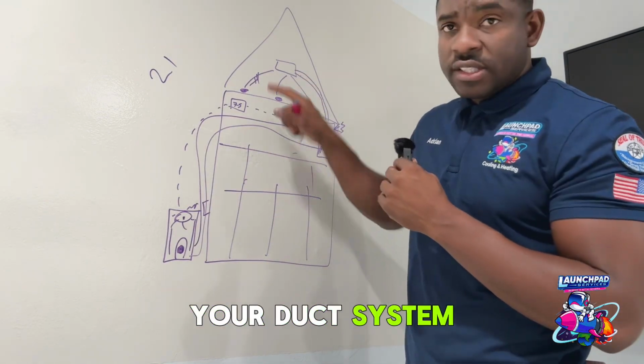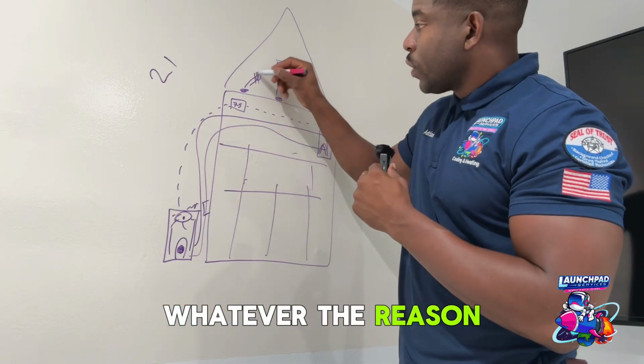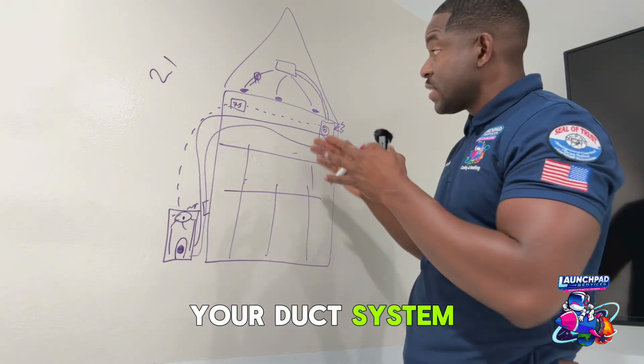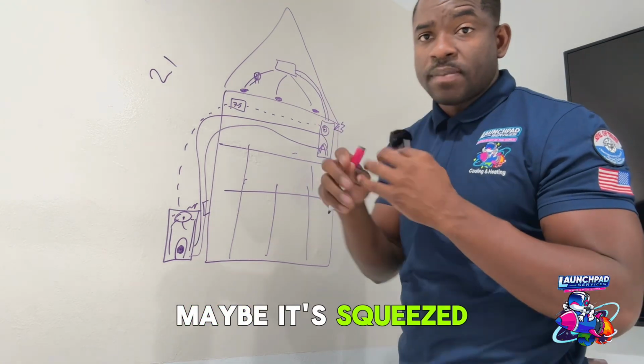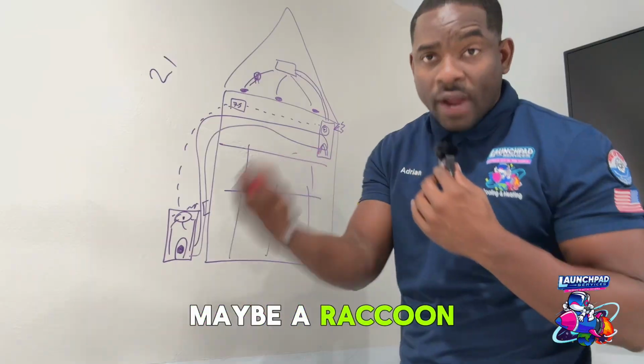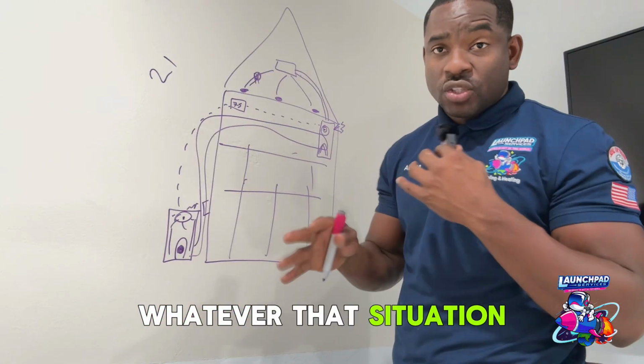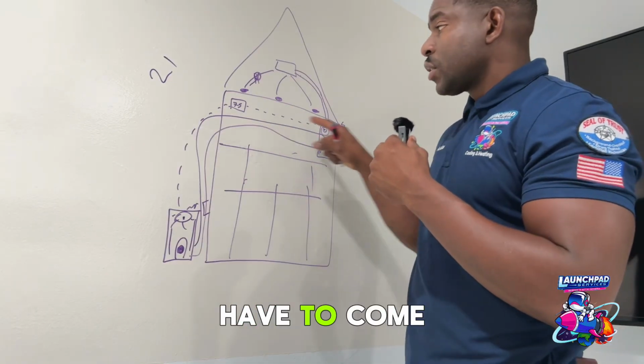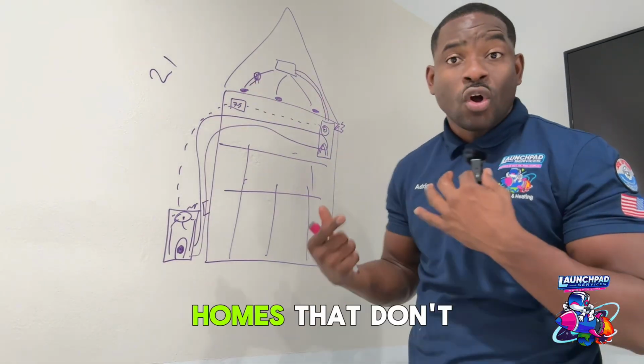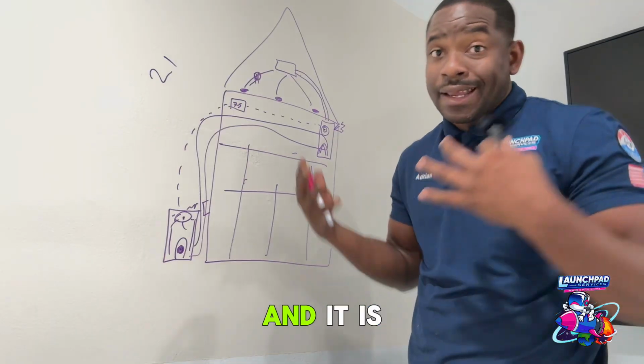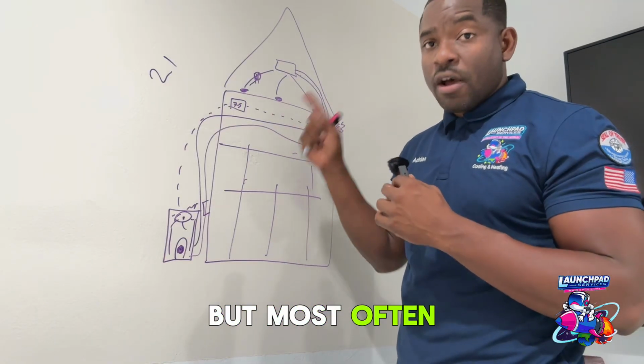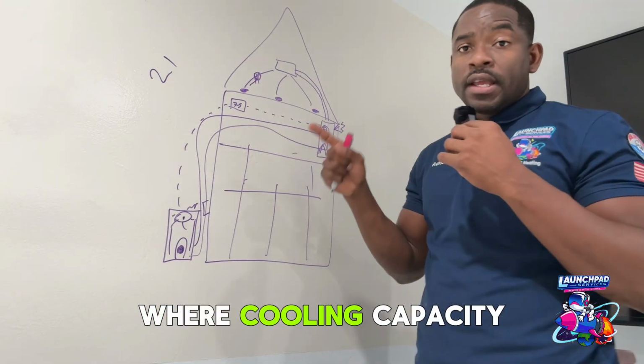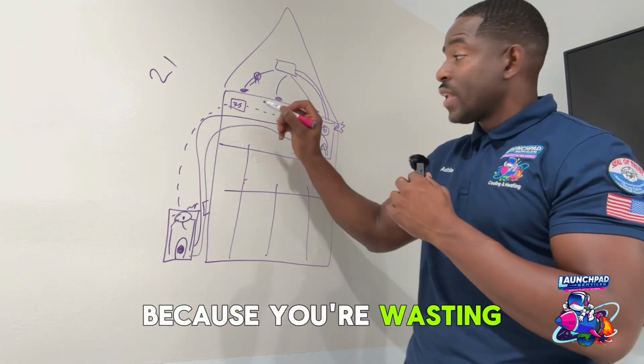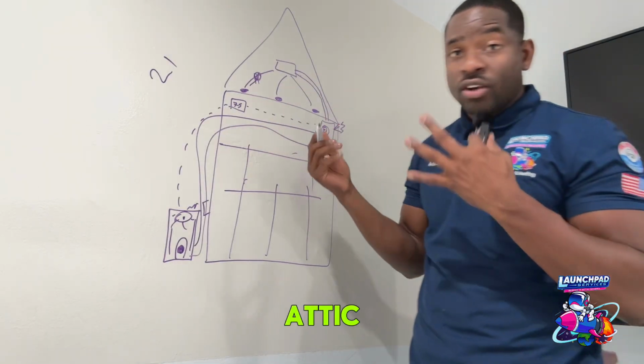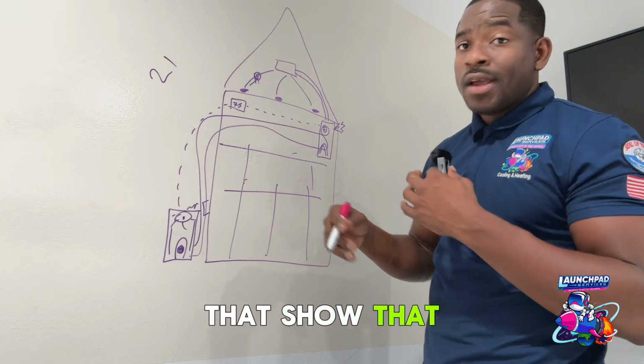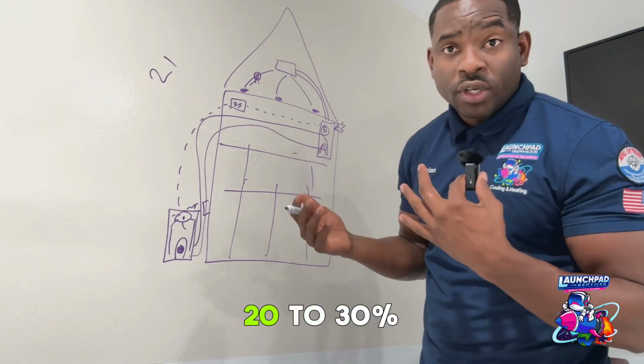We're also assessing your duct system. If everything works well, but for whatever reason your duct system is broken or has limited ability, maybe it's squeezed, maybe it's kinked, maybe it's just destroyed, maybe a raccoon went up there and you're cooling the attic. Whatever that situation is, we, the contractor, have to come up and take a look at it. If it is accessible, because there are homes that don't have really good access to ductwork, and it is what it is with those cases, but most often you're going to have a situation where cooling capacity goes down in the home because you're wasting about 30 to 40% of your air in the attic or whatever that number is. There are statistics that show that on average, the average homeowner probably loses between 20 to 30% of the air in the attic.